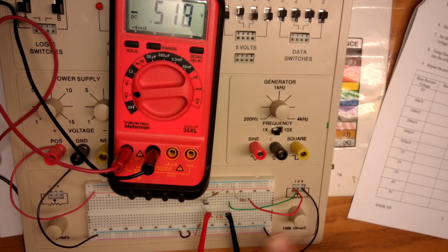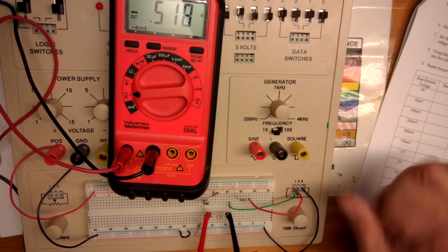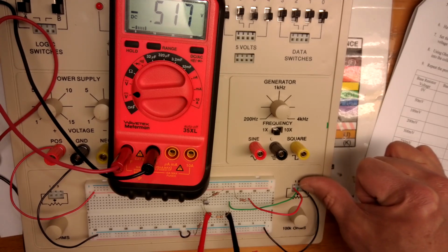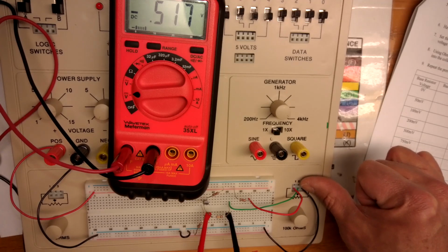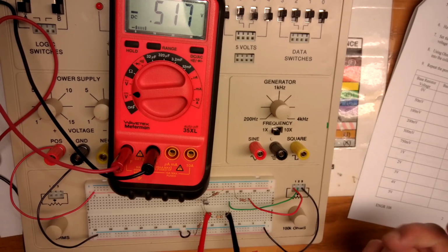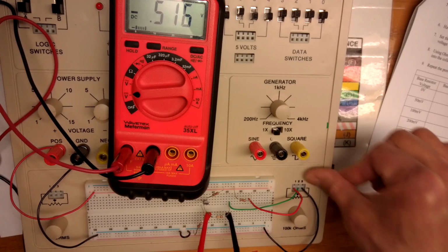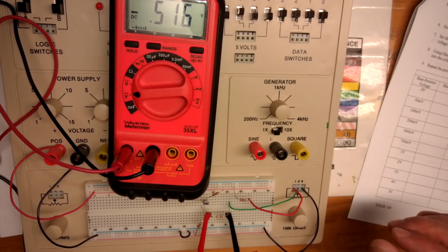Incidentally, if you have issues getting a voltage here, it's almost always because of these connections in here. Either one of them doesn't have enough wire stripped and it's not connecting, or it has too much and it's pushed down in, touching something inside. These connections are the first place I look to troubleshoot this.